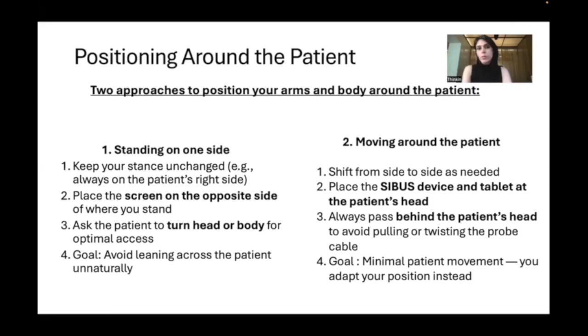Option two, you move around the patient. This is more dynamic and you change sides depending on the injection sites. So you place the SibUS probe and screen at the head of the patient to do so. And when you switch sides, you need to always pass behind the head to avoid twisting or pulling the cable. The advantage is that the patient doesn't need to move. You adapt instead. So both strategies work really well. You just need to choose the one that fits your habits and your room layout better. The goal always stays the same: visual alignment, ergonomic postures, and minimal strain for both you and the patient.